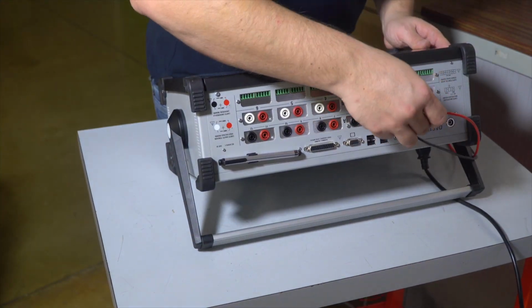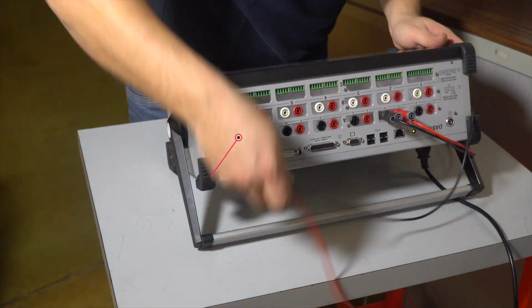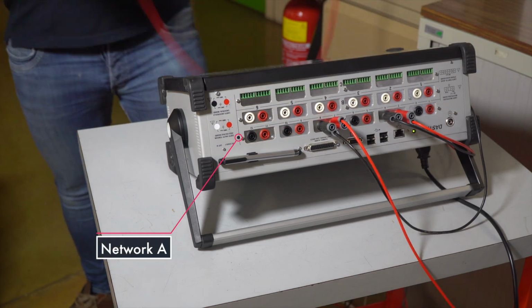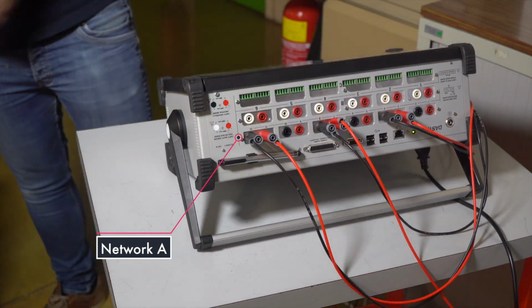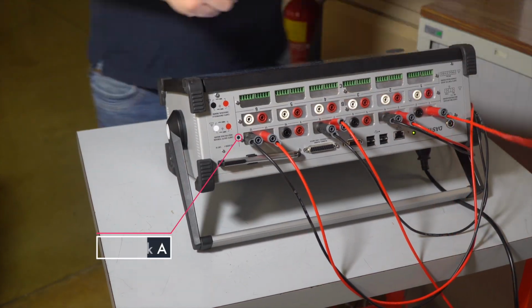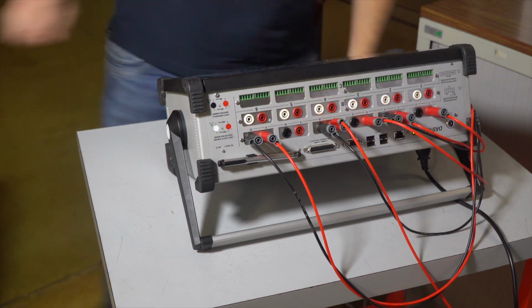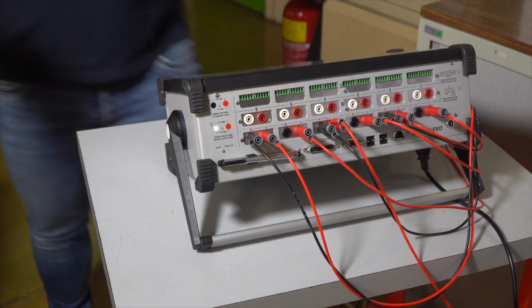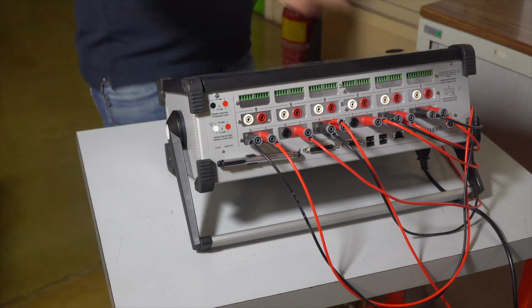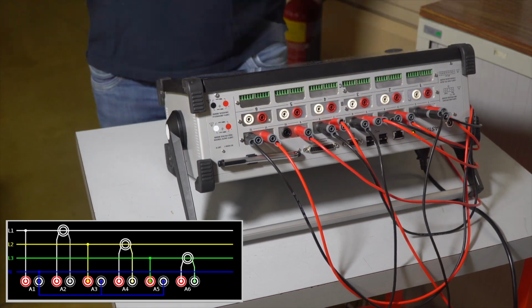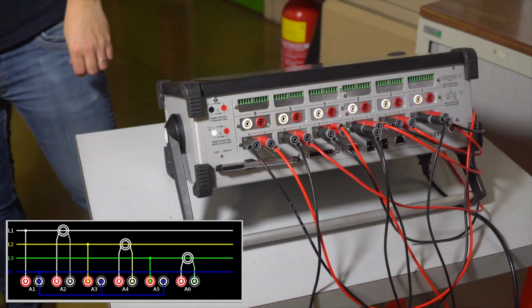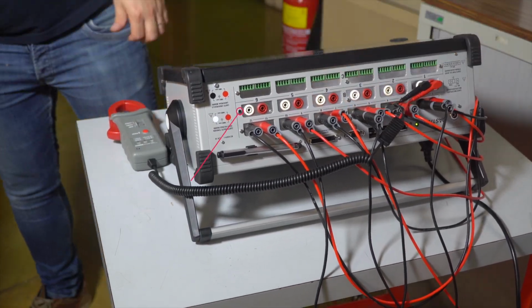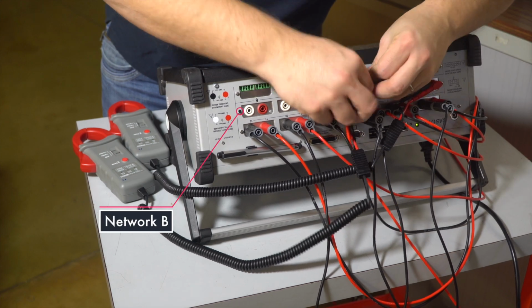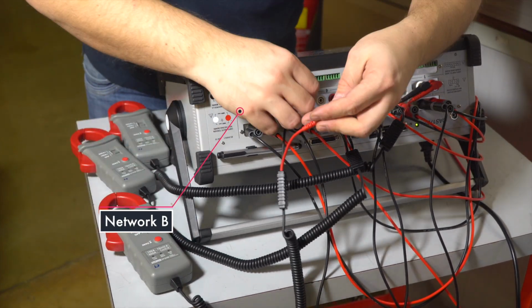In this example, we will analyze two electrical networks simultaneously, a main one and a secondary one. First of all, let's connect all the elements, such as current clamps and voltage measuring cords, to the instrument by following the diagrams shown on the instrument display. Then, wearing personal protective equipment, connect all these elements to our electrical installation.